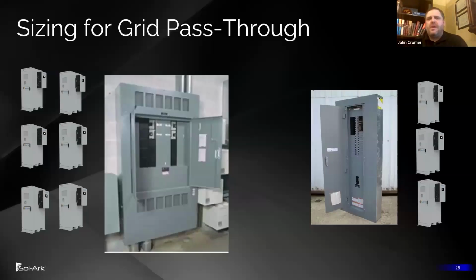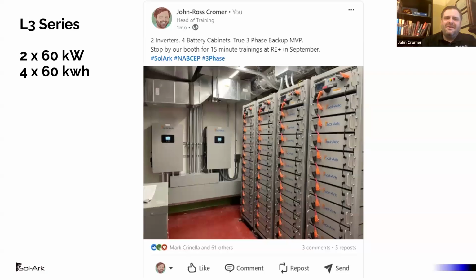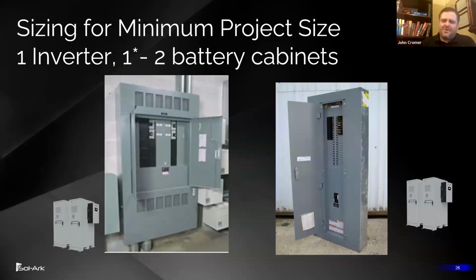This one, if you do a large service, that's fine. You can do a large service, but you're getting into multiple battery cabinets and multiple inverters in a detailed design phase. And I'm not trying to say don't do that. You don't want to leave money on the table. But if you don't have enough information for a detailed design phase, you've got 1 or 2 options. You can spend months and months and put in a lot of your own money trying to do the project development, chasing down that large project. Or you can say, hey, facility manager, you don't really know what you need right now, but you can afford the smaller system, 1 inverter and 2 battery cabinets.